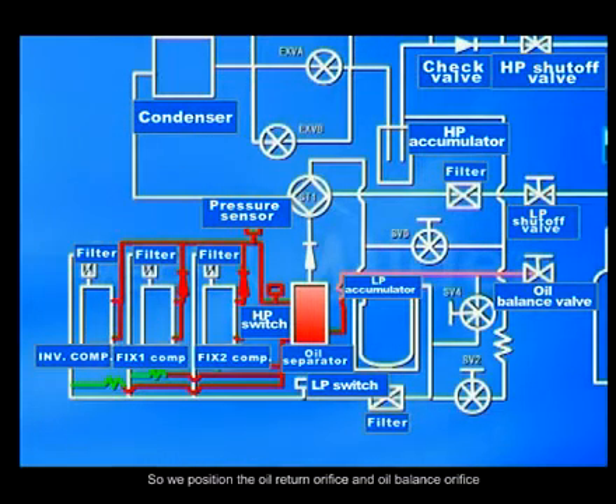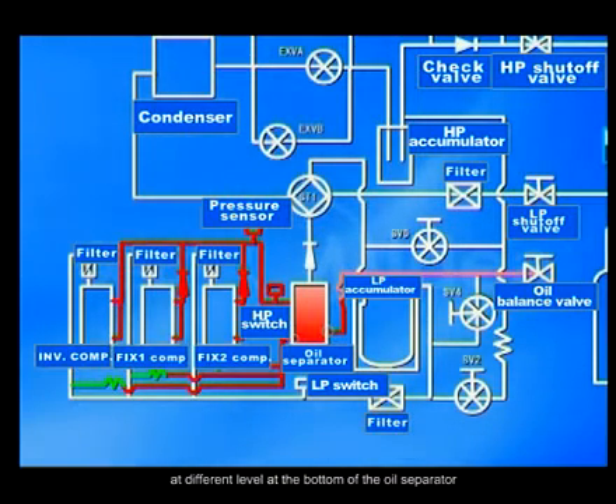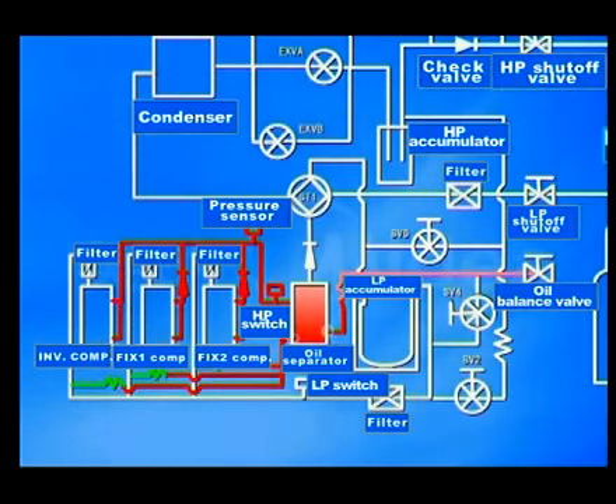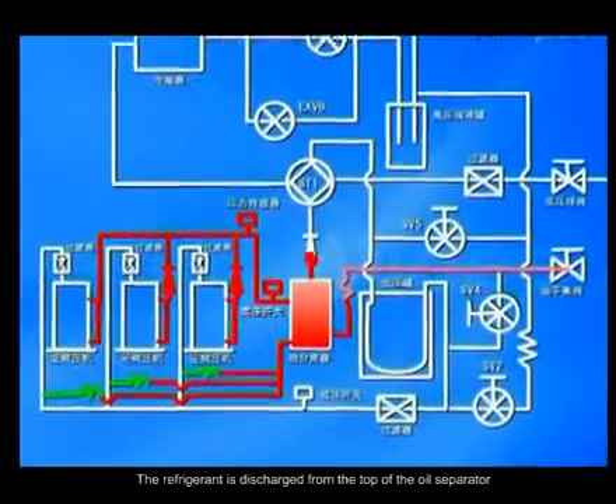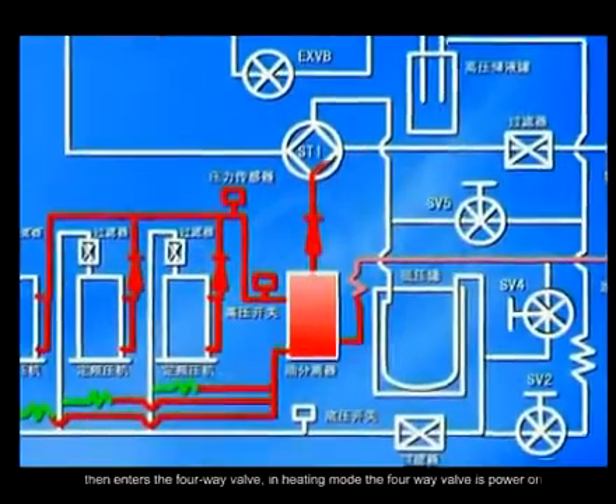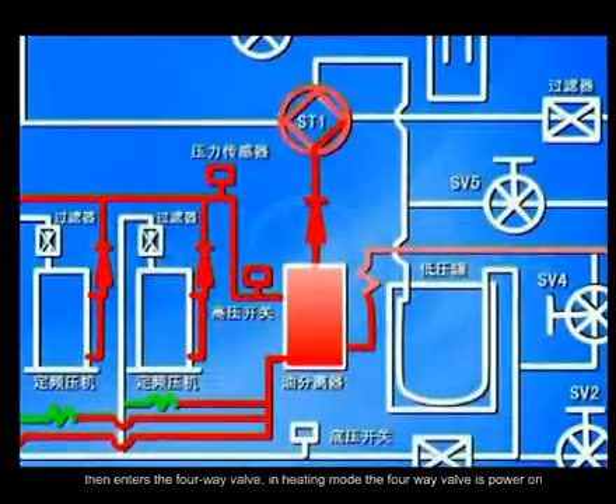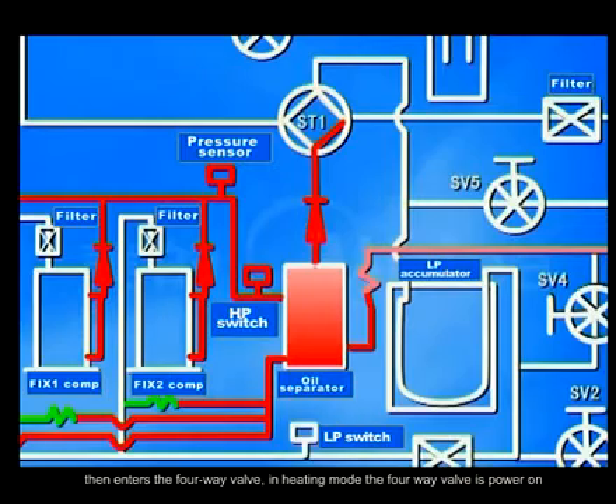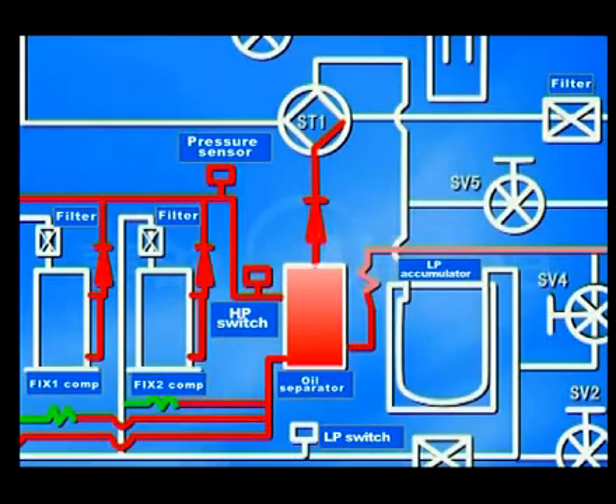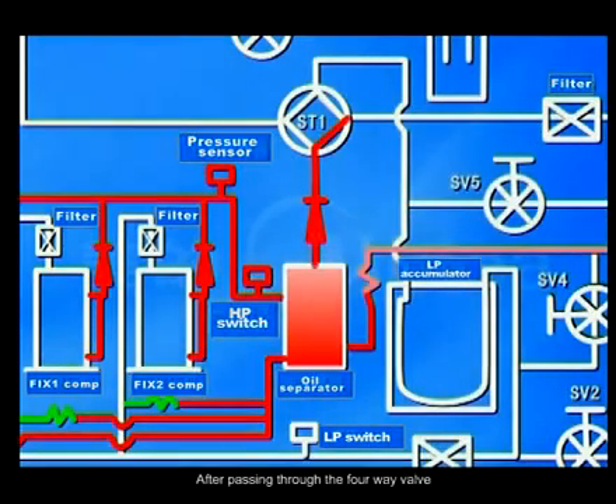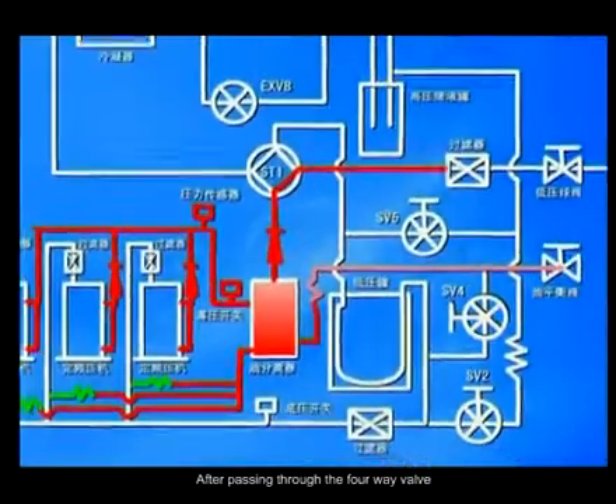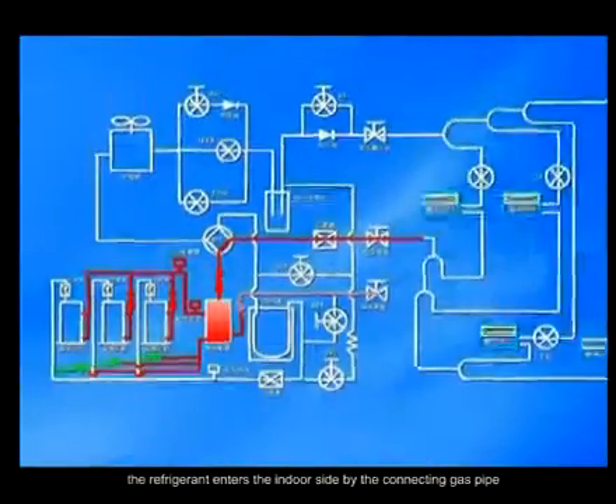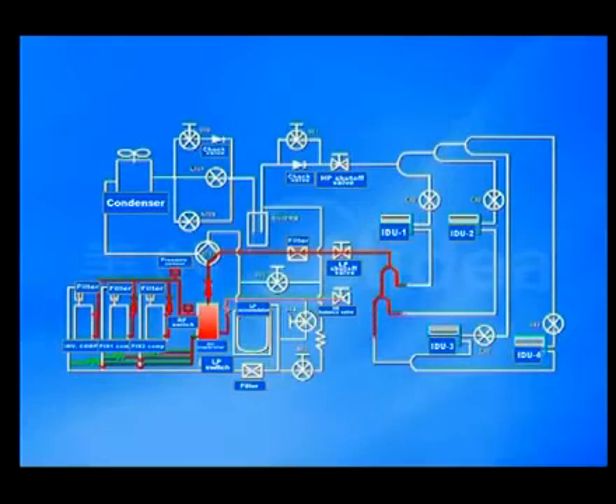So we position the oil return orifice and oil balance orifice at different levels at the bottom of the oil separator. The refrigerant is discharged from the top of the oil separator, then enters the four-way valve. In heating mode, the four-way valve is powered on. After passing through the four-way valve, the refrigerant enters the indoor side by the connecting gas pipe.